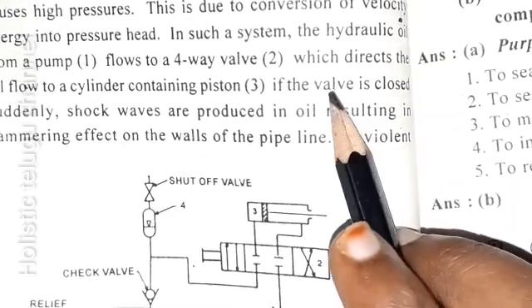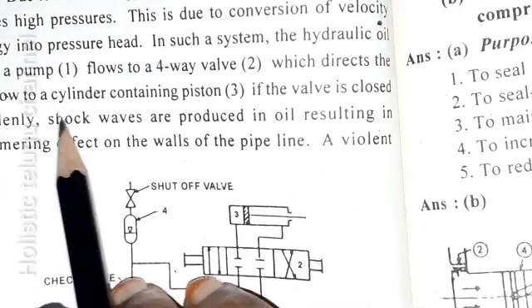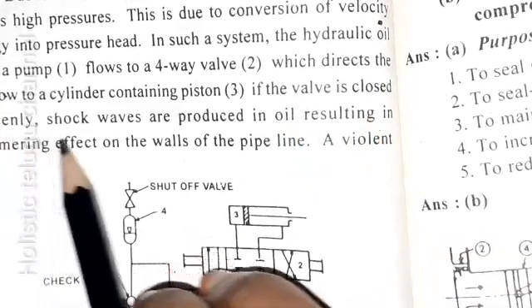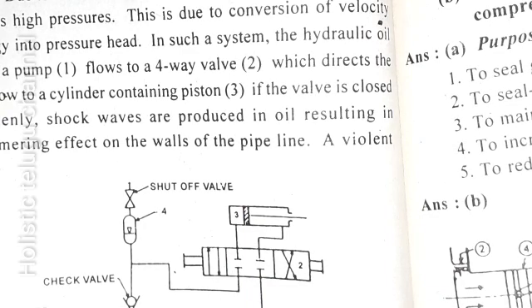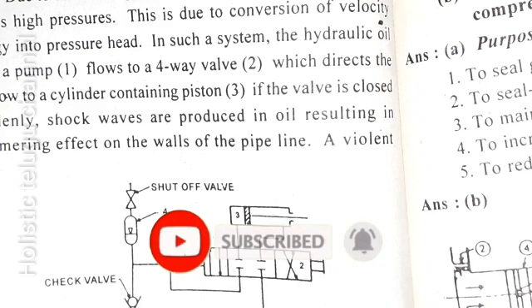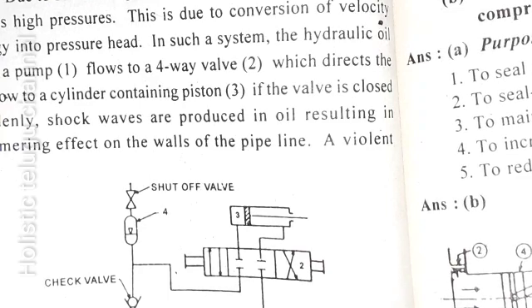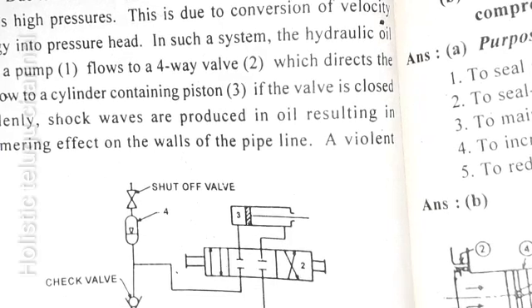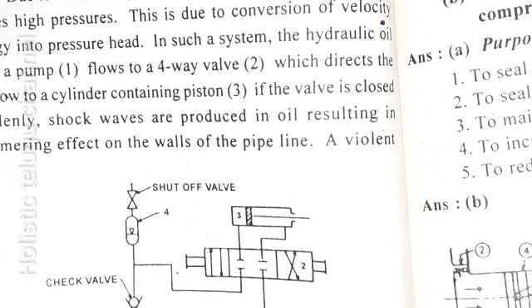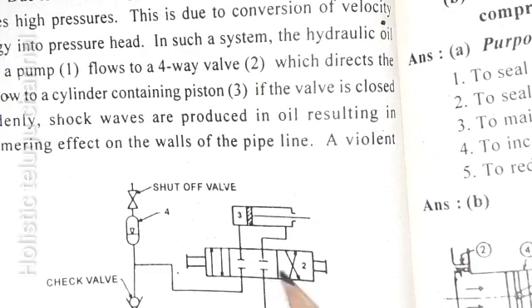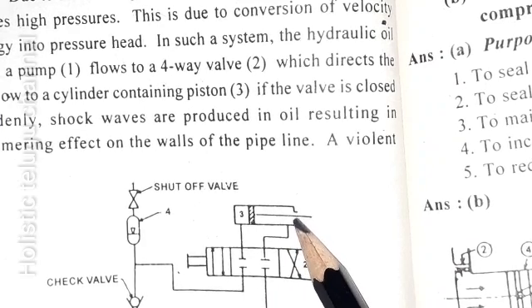This is due to conversion of velocity energy into pressure head. In such a system, the hydraulic oil from pump flows to the 4-way valve which directs the oil flow to cylinder containing piston. If the oil valve is closed suddenly, shock waves are produced in the oil resulting in a hammering effect. A violent hammering effect will damage fittings and pipes.